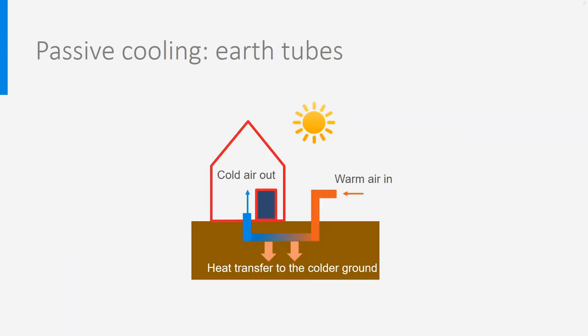Let's look now at the potential of the ground. In general, the shallow ground is colder than outdoor air during the hot season. There are therefore passive systems making use of this by circulating the outdoor ventilation air through pipes in the ground, so-called earth tubes. The air is then cooled by the ground. Similar systems are used by having the air circulating in a cool basement, for instance. It is important to take care that pipes and basements are clean and that no condensation occurs to maintain a high air quality. If the pipes become humid because the water vapor condensates on its surface, it can facilitate mould growth and the air can smell stuffy. As for the sizing of these pipes, which may need quite some length, it is all about the conduction heat transfer between the pipe and the ground and the convection heat transfer in the pipe.